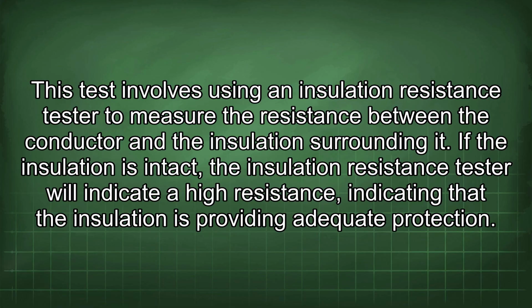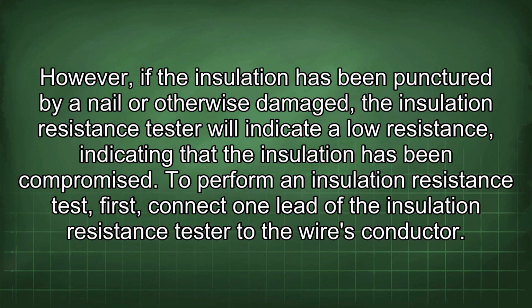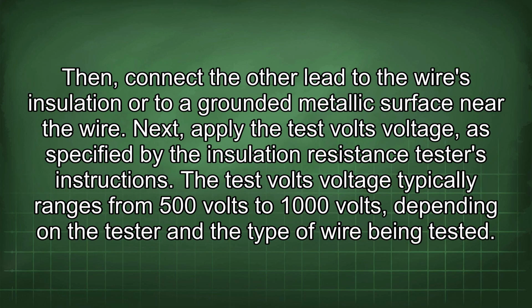If the insulation is intact, the insulation resistance tester will indicate a high resistance, indicating that the insulation is providing adequate protection. However, if the insulation has been punctured by a nail or otherwise damaged, the insulation resistance tester will indicate a low resistance, indicating that the insulation has been compromised. To perform an insulation resistance test, first connect one lead of the insulation resistance tester to the wire's conductor. Then, connect the other lead to the wire's insulation or to a grounded metallic surface near the wire.